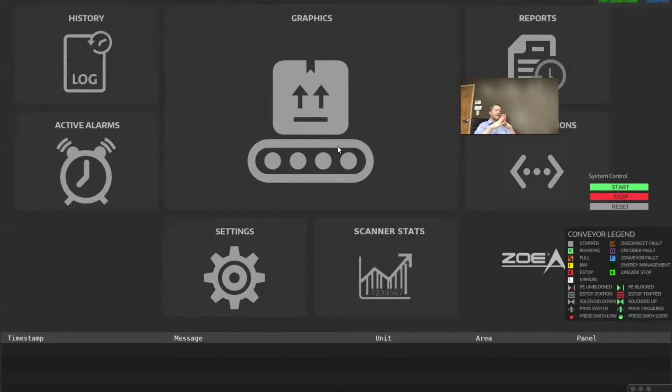Okay. Because a majority of the time the customer doesn't need to look back that far. And if you're keeping that information, these tables have to sort through it, so it's longer queries and it slows down the system. So it's good to clean it up. But that's adjustable based on the customer's needs. Some customers will only keep like 10 days of information because so much information is coming in. Some of them it's 45 days.